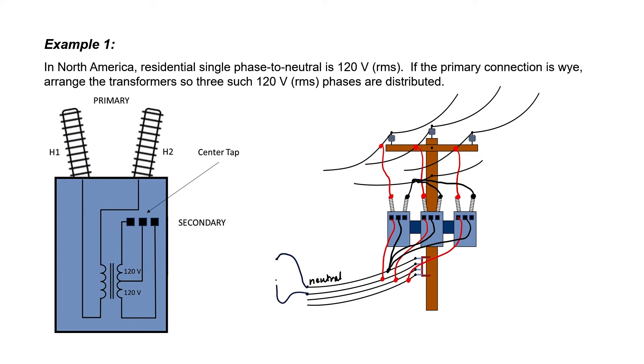If I were to take a voltmeter and now measure the voltage difference in RMS between any of these three phases to neutral, I would get 120 volts RMS. On the other hand, if I were to measure the voltage between any of the three phases, then I would measure 208 volts RMS. That's 120 times the square root of three.